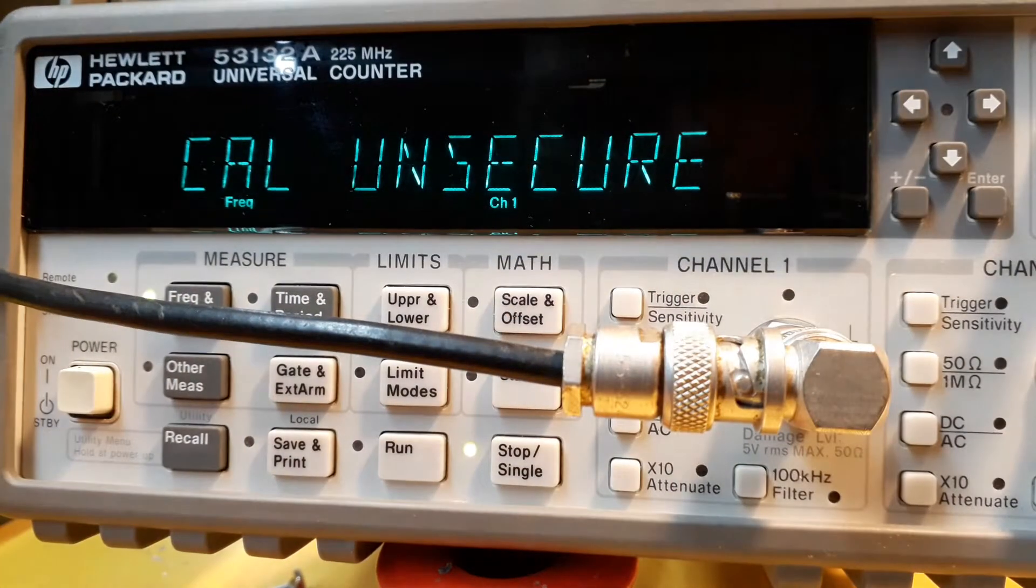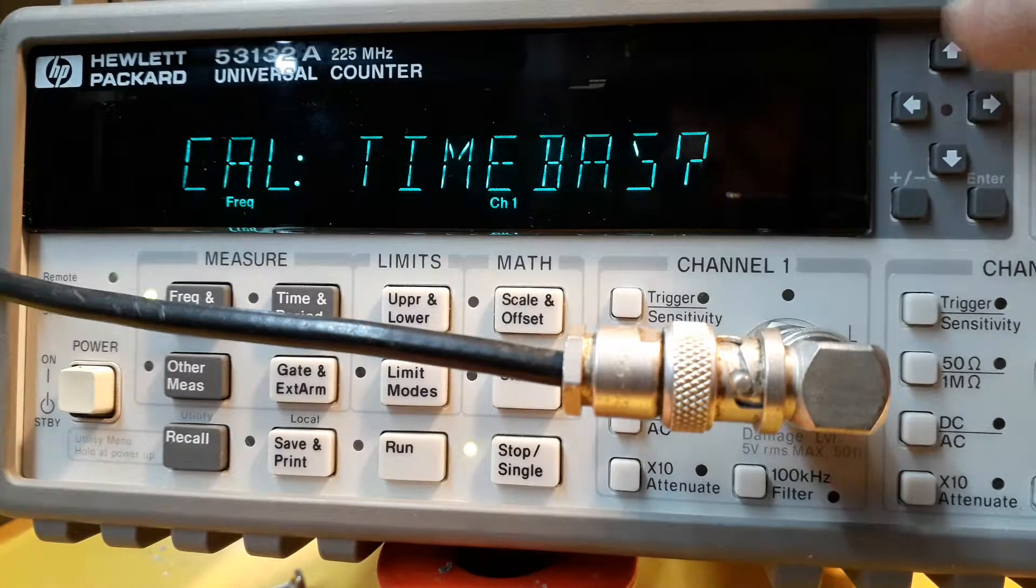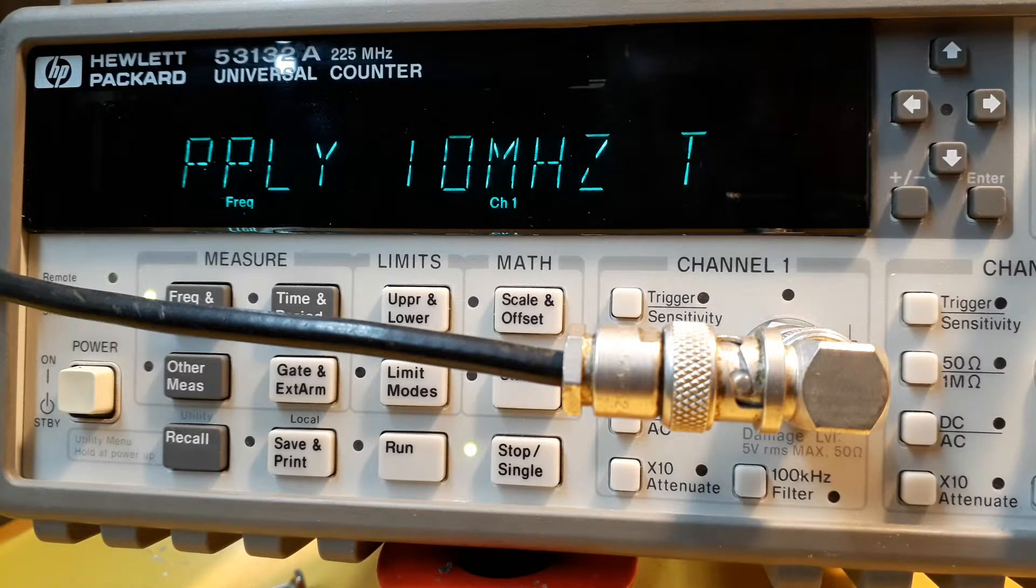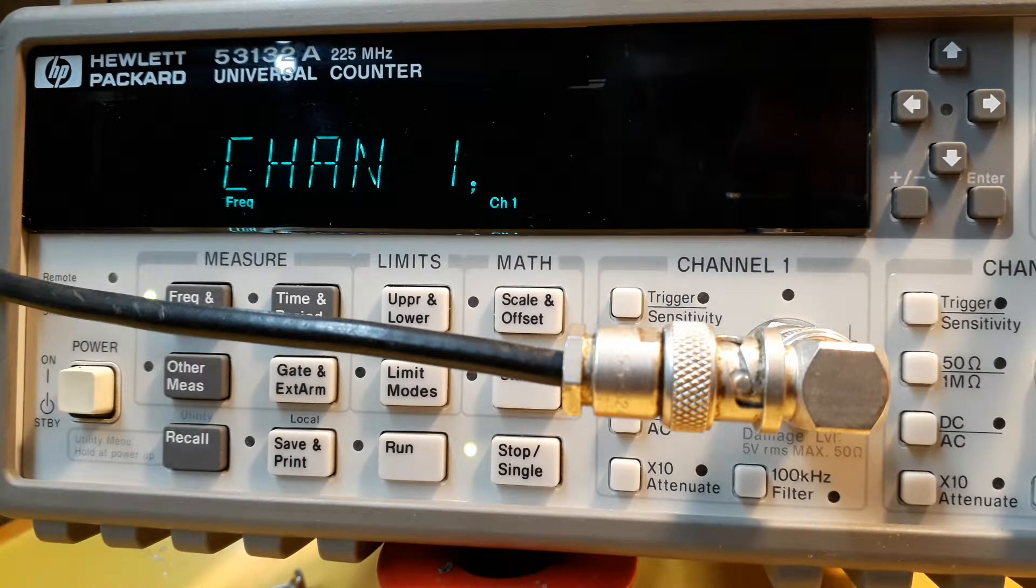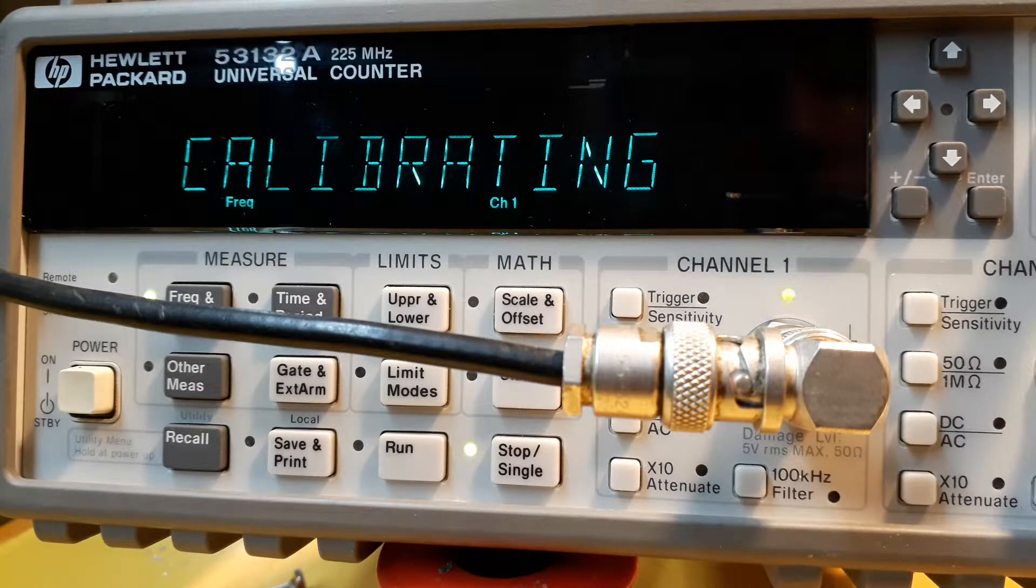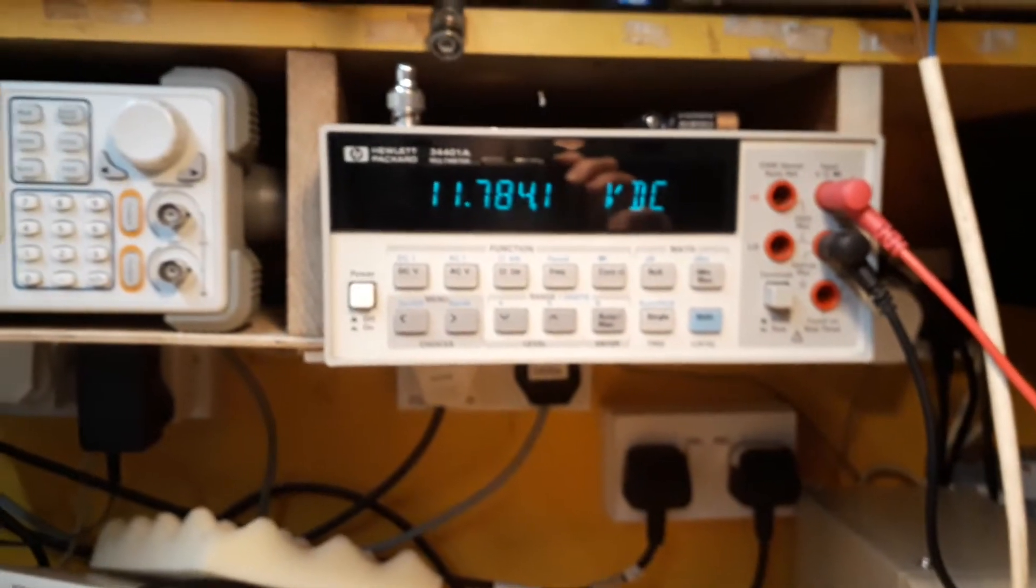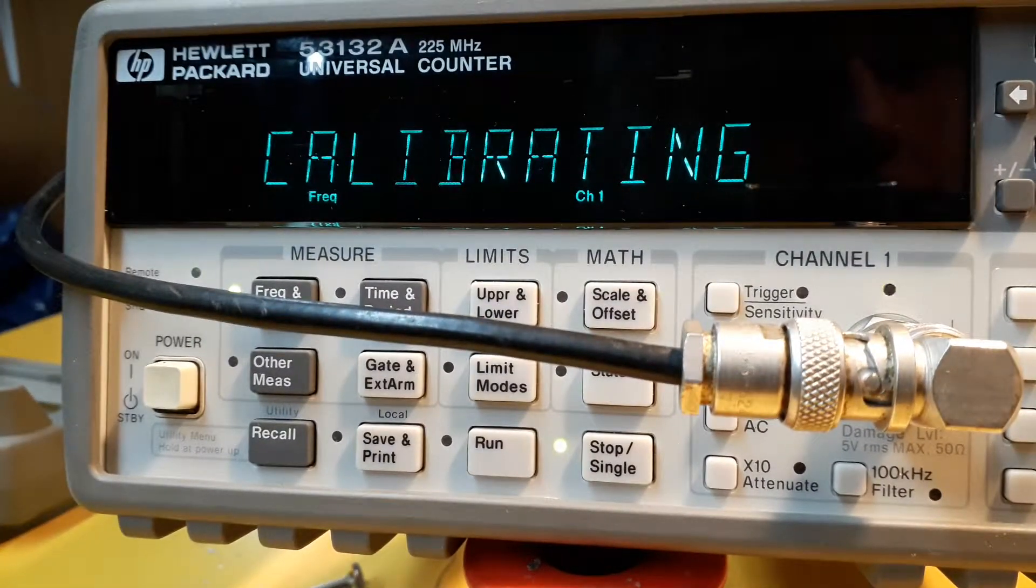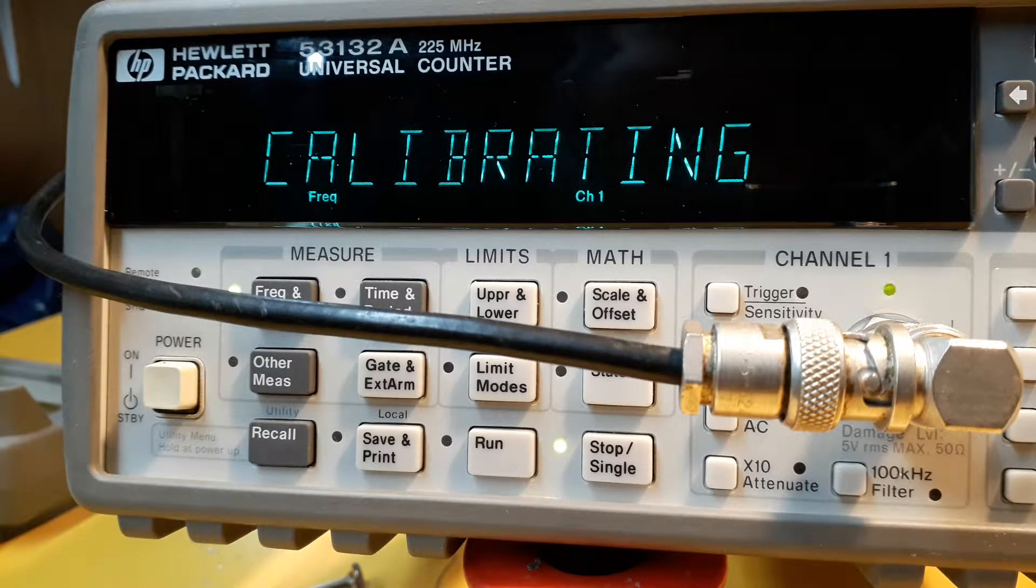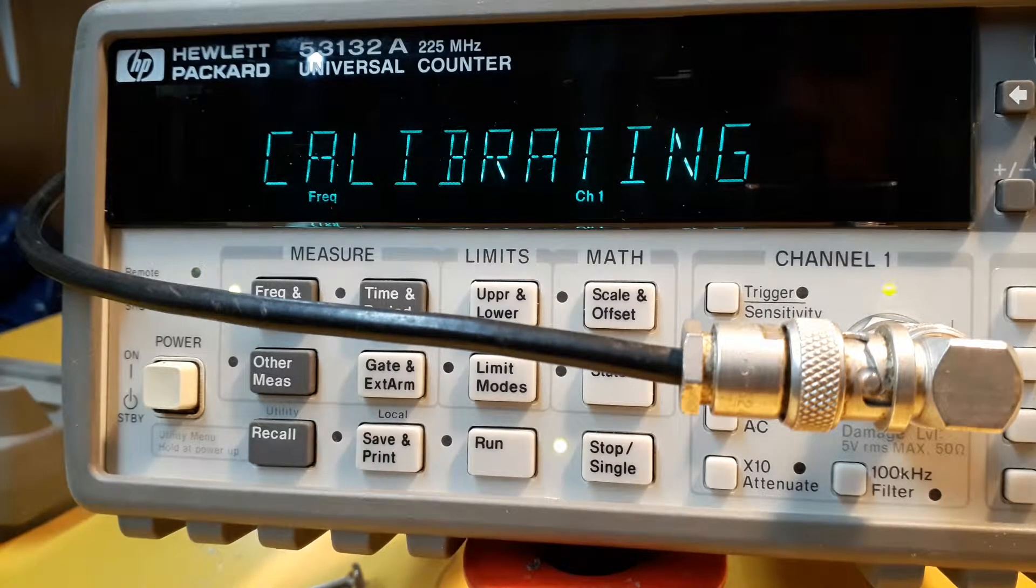Okay, and select time base and enter. Right, enter. Calibrating. Fine. Takes a while to do this. And what I'll be reading now, 11.78 volts on the 12 volt rail. I suppose that's reasonably good considering the volt drop on that thin wire. This takes a few minutes I think to do this. I'll just pause it.